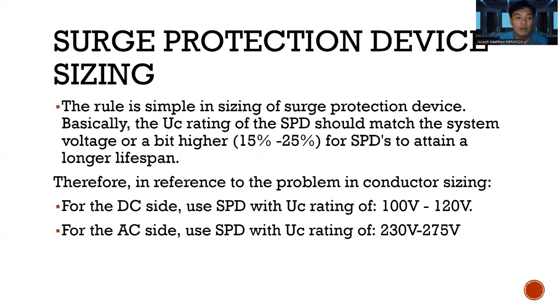So, surge protection device sizing. The rule is simple in sizing of surge protection device. Basically, the UC rating of the SPD should match the system voltage or a bit higher. Add 15 to 25% for SPDs to attain a longer lifespan. Therefore, in reference to the problem in conductor sizing, for the DC side, use SPD with a UC rating of 100 volts to 120. So for DC daw, gagamit tayo ng 100 to 120 volts. For the AC side, sa AC side naman tayo, use SPD with UC rating of 230 to 275. So mas mataas siya.